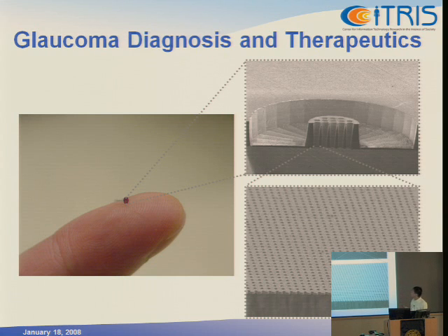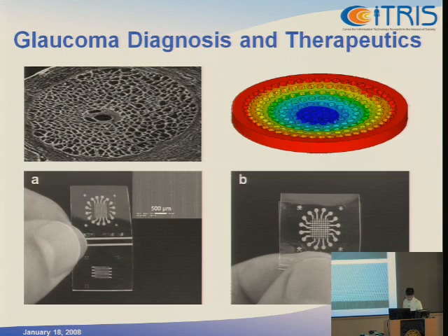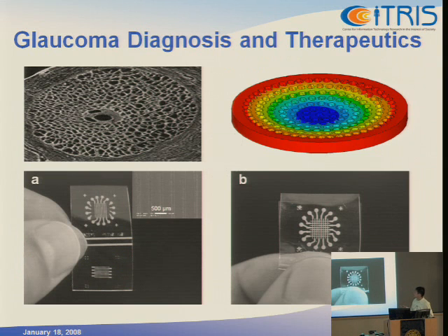The problem with this first generation device was that because it's based on silicon technology, the surface coating we put on, a biocompatible polyethylene glycol polymer, is not good enough to prevent proteins clogging the channel. So currently we're working on a pure polymeric substrate for the whole device, and looking forward to moving to animal testing.